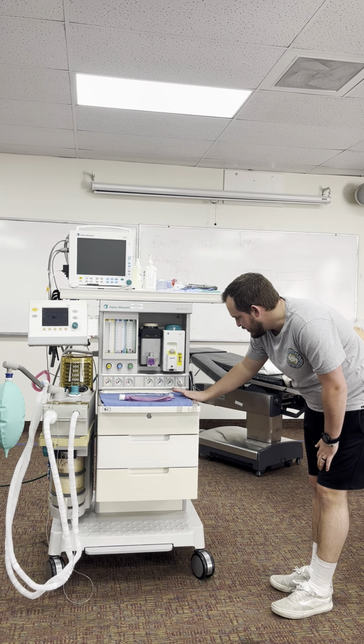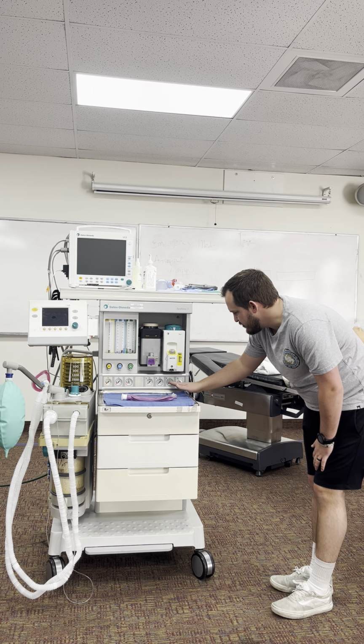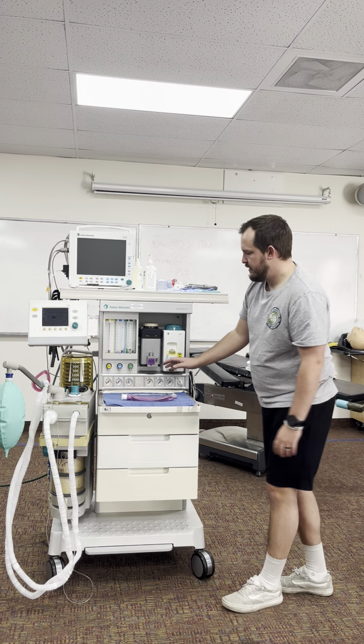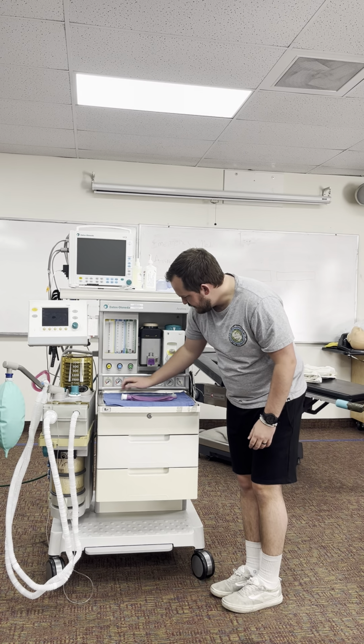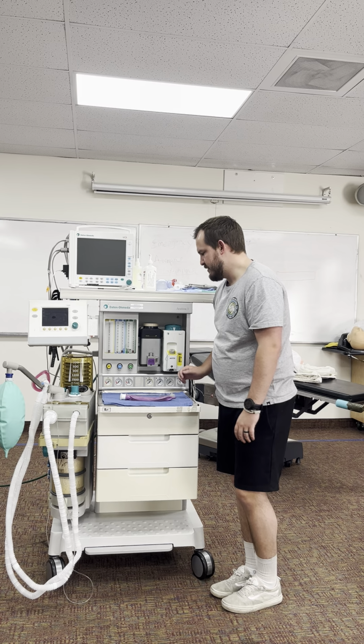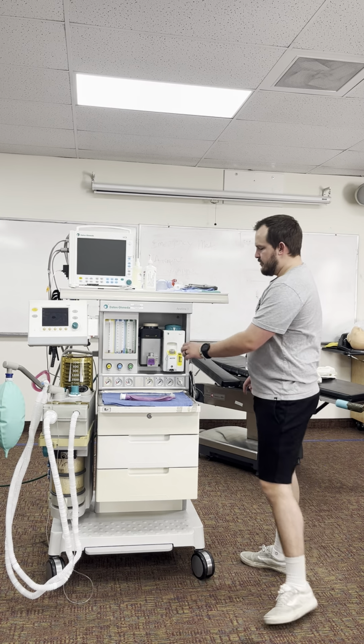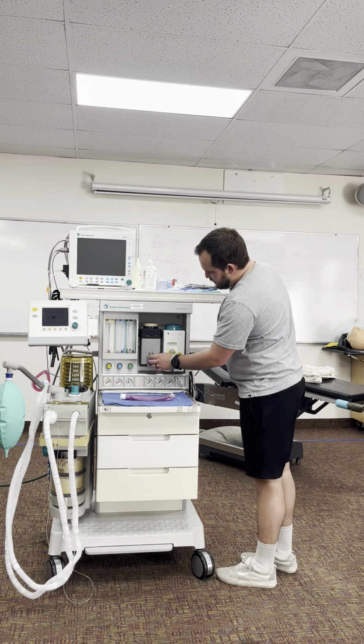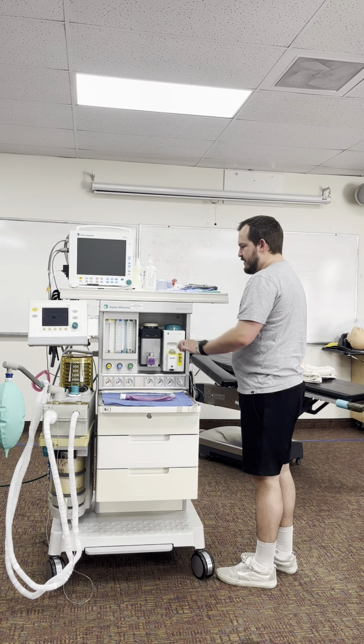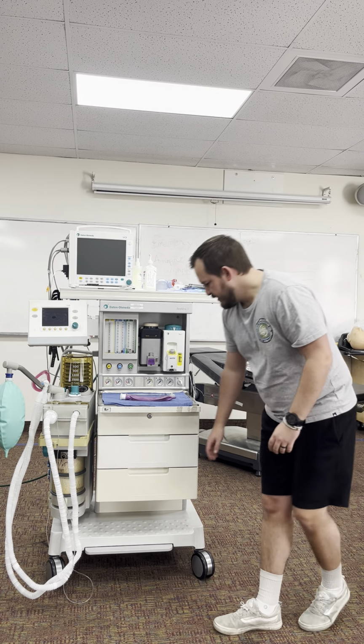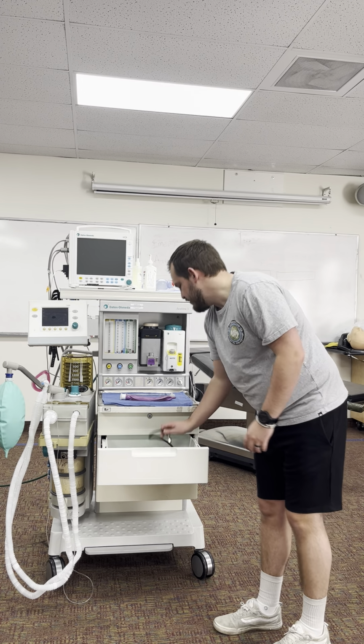So specifically, my oxygen needs to be at least 1,000 PSI, which it is, and then my pipeline pressure should all be at least, or about 50 PSI, which they are. And then I'm going to look at my vaporizers. I'm going to make sure that they're full and that the caps are on tight. They are, so that's good. And I'm going to move forward and do a low pressure test.